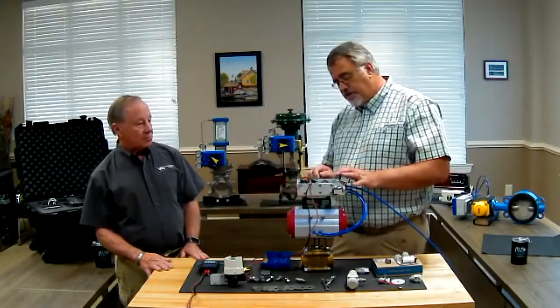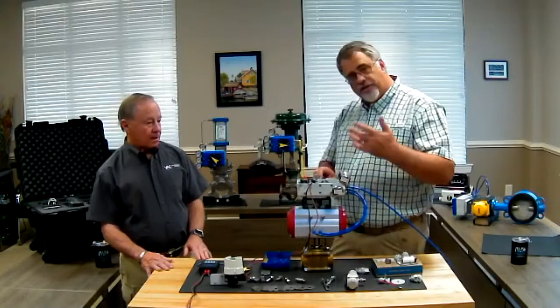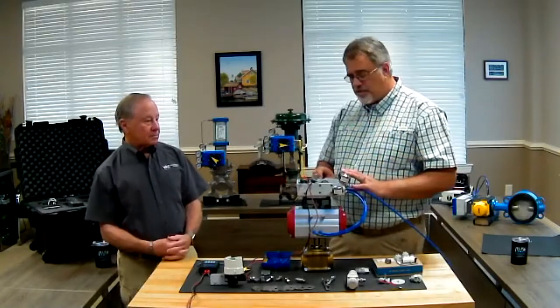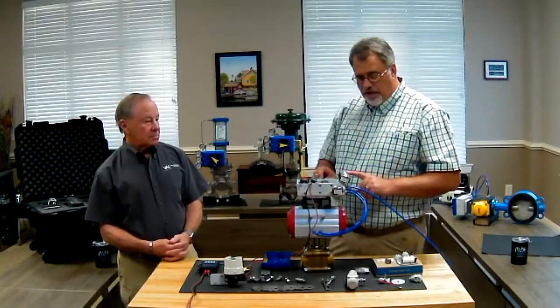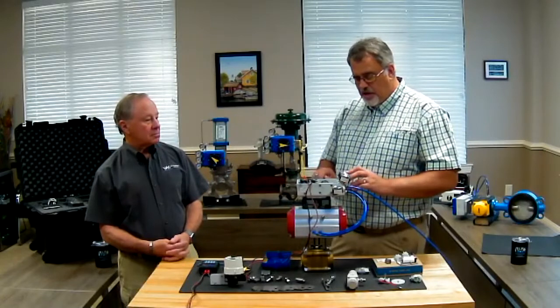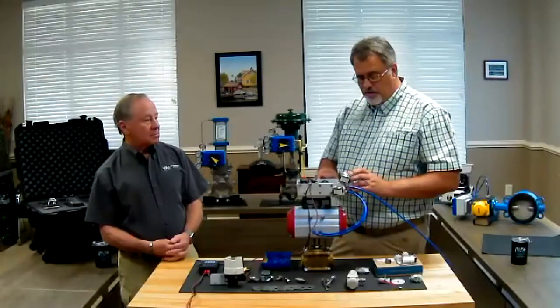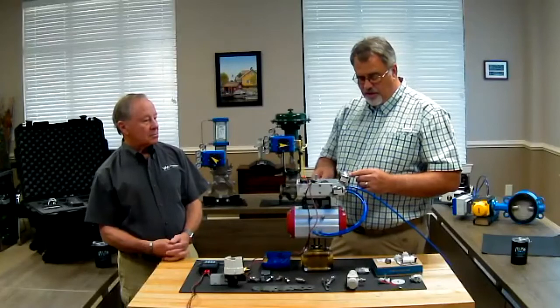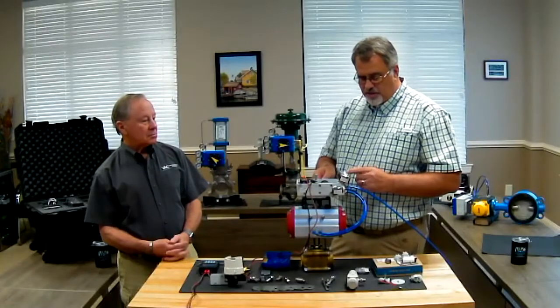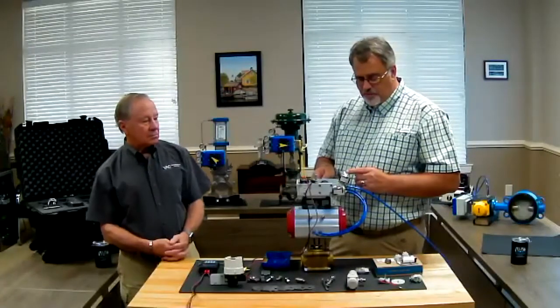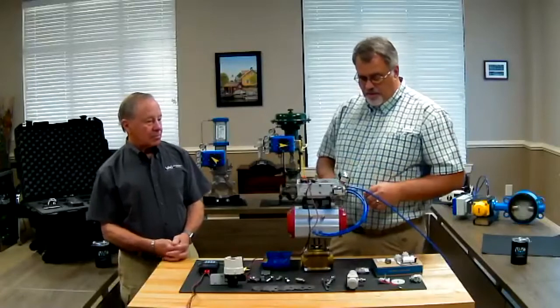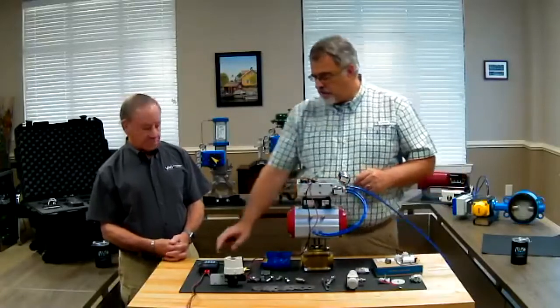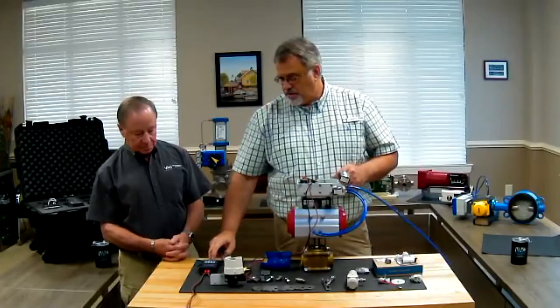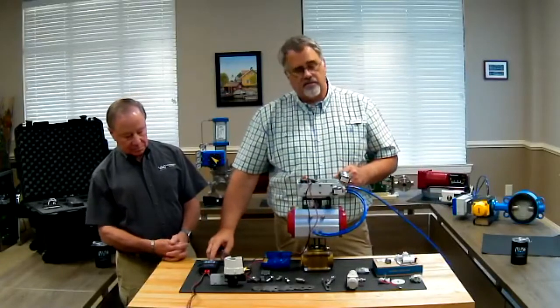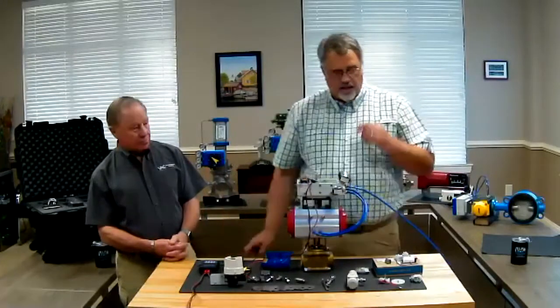Again, there are YouTube videos that show this in detail, but I'm showing you this to show you how quickly this can be done. So I'm going to look at my gauge here, and I'm going to turn this zero screw just until the needle comes off the pin, and back it down until the needle just lightly rests on the 0 PSI mark. By bouncing that arm, I can watch how fast that works, and that's within the 3 to 5 second time frame that we're looking at on our calibration instructions.